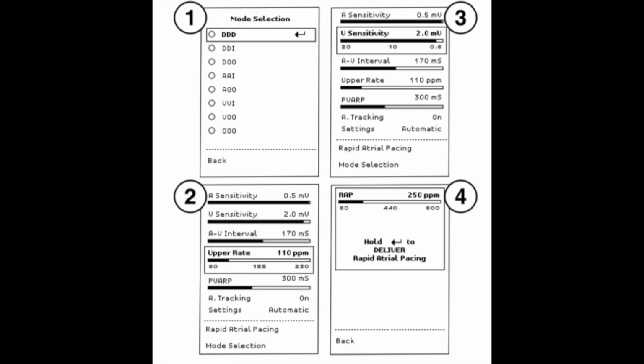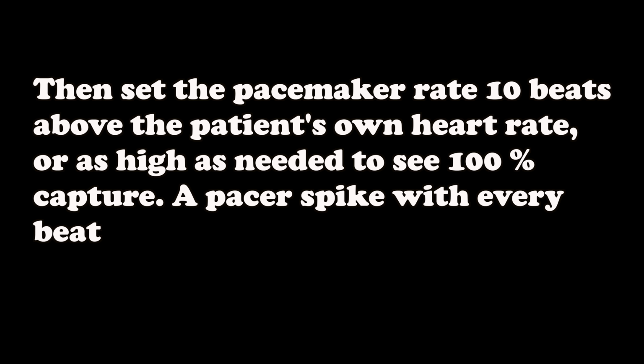Before determining the stimulation threshold, make sure the pacemaker is in demand mode. Then set the pacemaker rate 10 beats above the patient's own heart rate, or as high as needed to see 100% capture. A pacer spike with every beat.